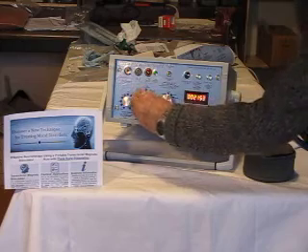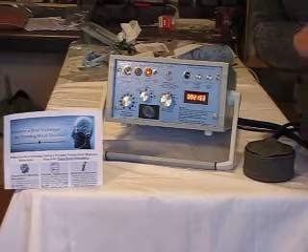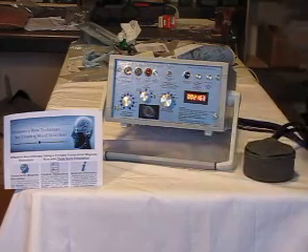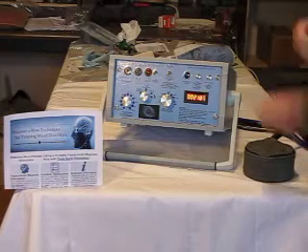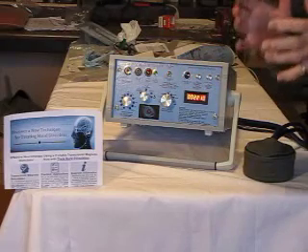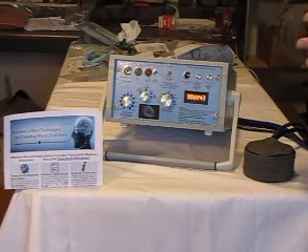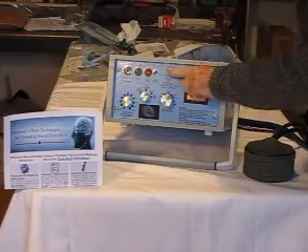This position here is the external input, so you can input from a microcomputer any algorithm or program yet to be devised in the future. And this position here is the theta burst at five per second. The theta is on or off with this switch — theta burst means a burst of high-frequency pulses gated on and off five per second, which is the theta frequency.